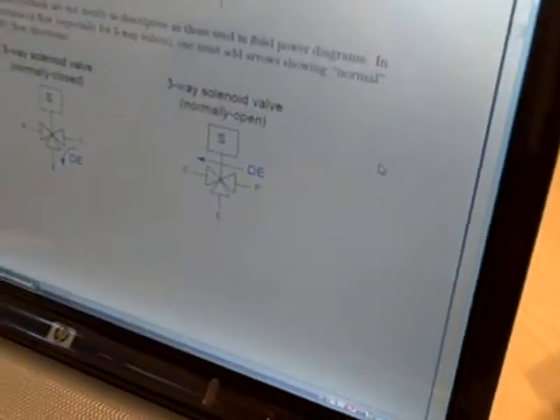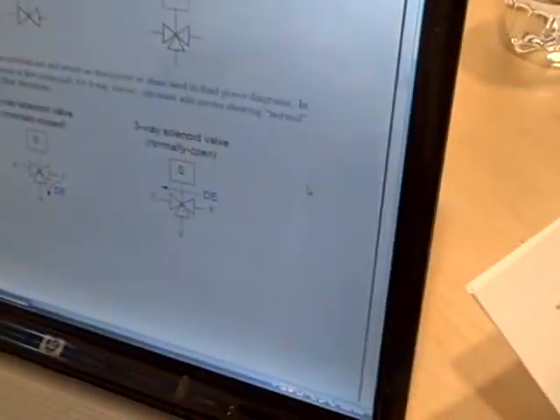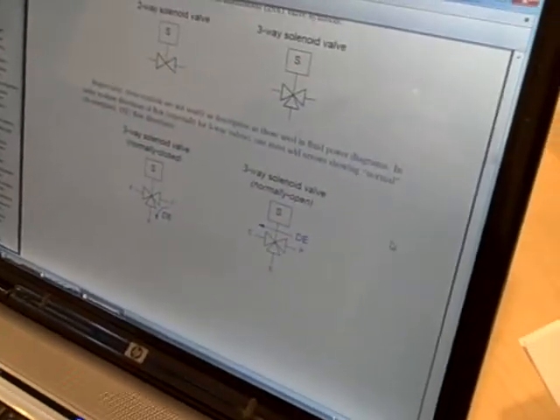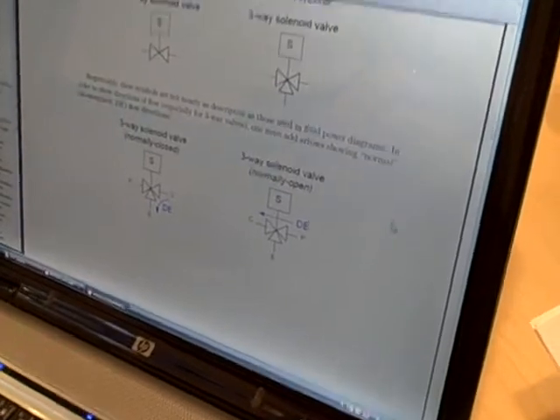And I'm with you, I tend to find those designations easy to understand, where there's an E for energize and a D for de-energize. You will, though, often see this, so just show one of those states and have you fill in the blank for the other, previous page. Right there. So notice here, they only show us the de-energize state, or they may only show us the energize state and just let you figure out the other one. I don't like that as much because it's a little bit more ambiguous, especially if you don't have the P, E, and C labels. Yeah, you don't know if the pressure is venting or if the cylinder is venting. You just have to tell by context. But I found that to be typically more common in P&IDs than to show both ways, like you see right here.